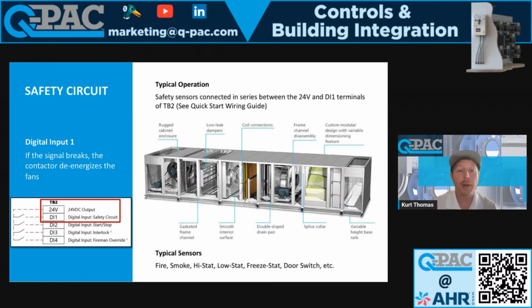You may want to bypass our safety circuit if you're just starting up our system and you want to do a bump test and you've got power. Then you can put a wire in between 24 VDC and digital input 1, and that'll bypass the safety circuit, and you can just put it in hand mode. That's a really common method every time after an install, just to do a bump test.